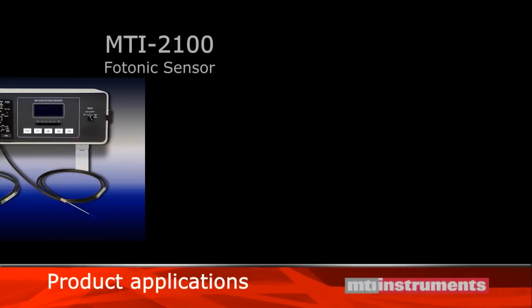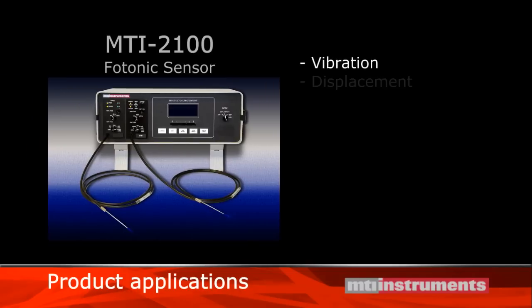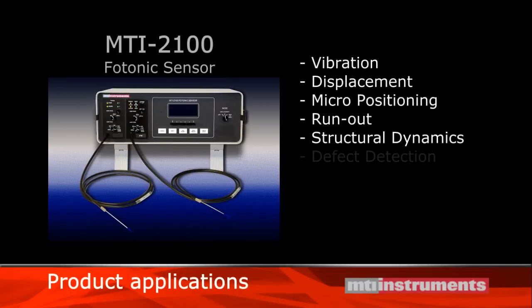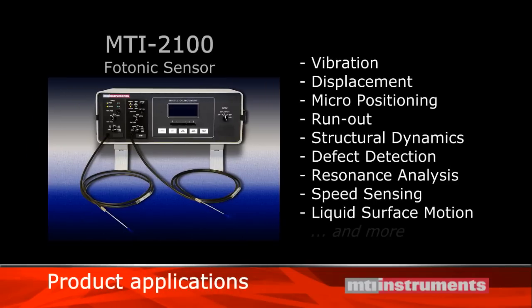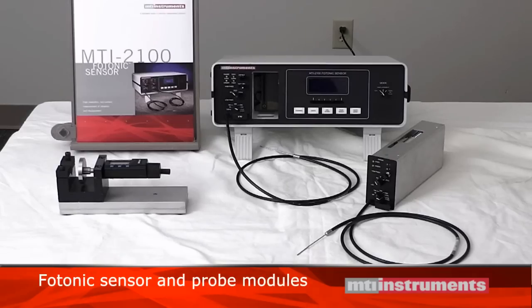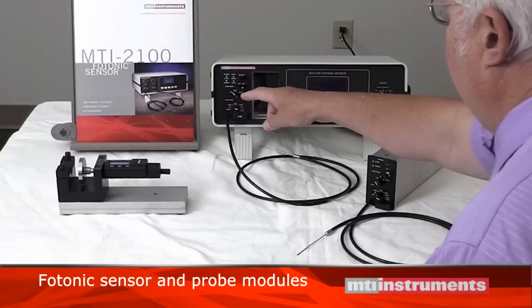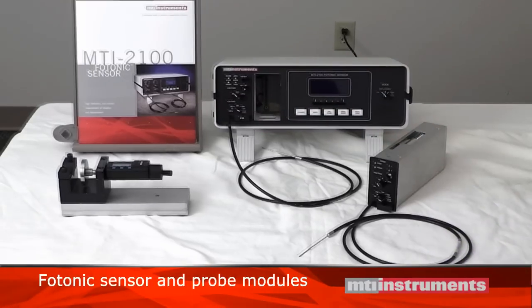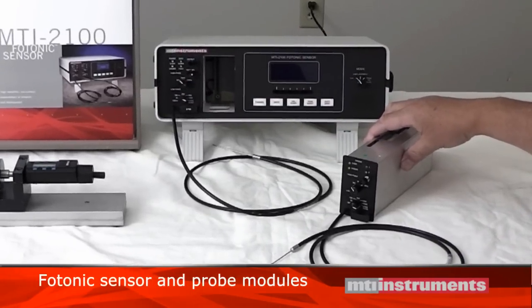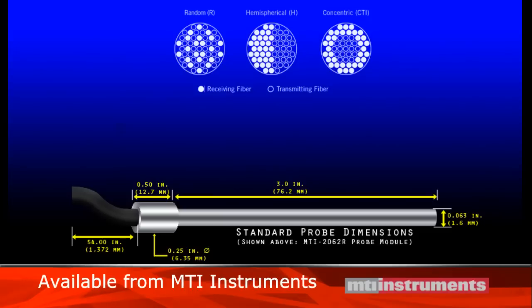I will show you how to calibrate the MTI 2100 Photonic Sensor. The Photonic Sensor is a high-resolution, non-contact fiber optic sensor that measures vibration and displacement on a wide variety of materials. First, let me show you the instrument and identify each part. This is the MTI Photonic Sensor mainframe with two probe module bays. And here we have a typical probe module.